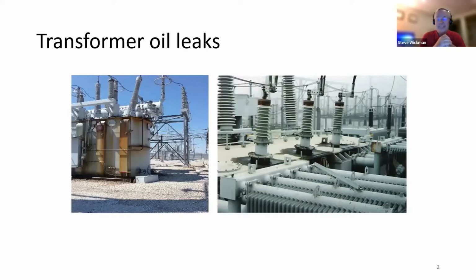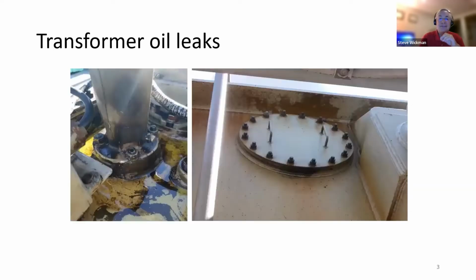Transformers leak oil, as is depicted in these couple of pictures here, which are some rather drastic scenarios. And there's not only just bushings, but other different components can have oil leaks also. On the left, you see a sudden pressure relay, sometimes called a fault pressure relay, mounted on top of a transformer. This is a conservator style transformer, so the oil is all the way up in the tank. And needless to say, the flange on this device has failed.